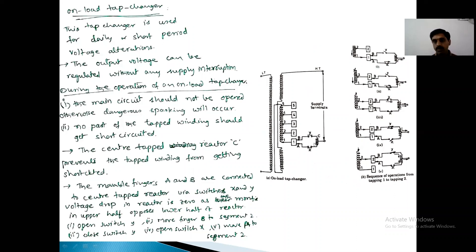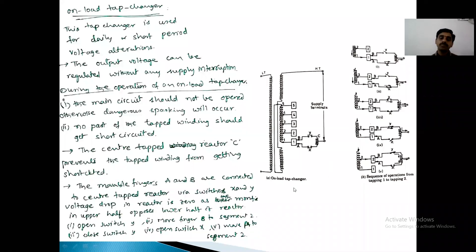The center-tapped reactor prevents the tapped winding from getting short-circuited. Otherwise, when both taps are connected, there is a short circuit current flow — the two currents flow in a closed loop and the winding gets short-circuited. That is why we use a center-tapped reactor. This is about the tap changing transformers.